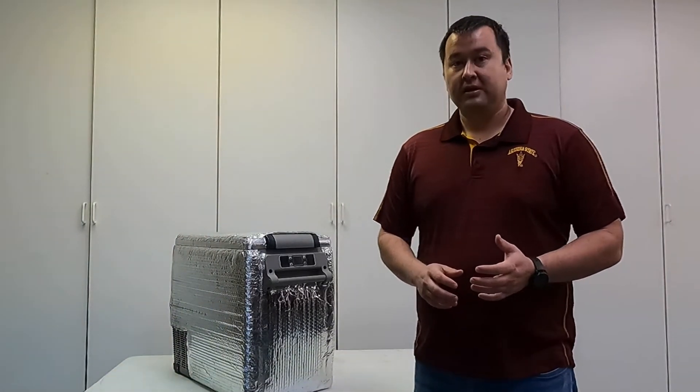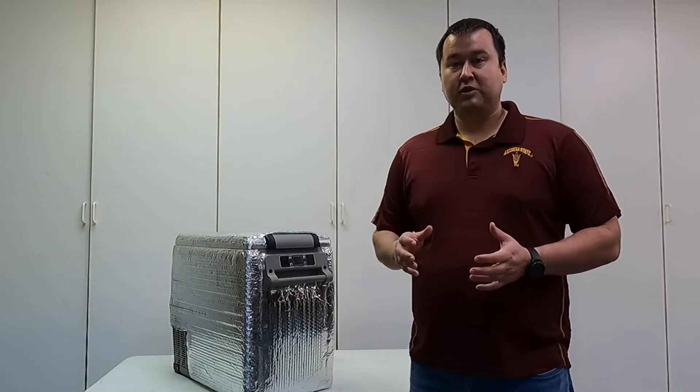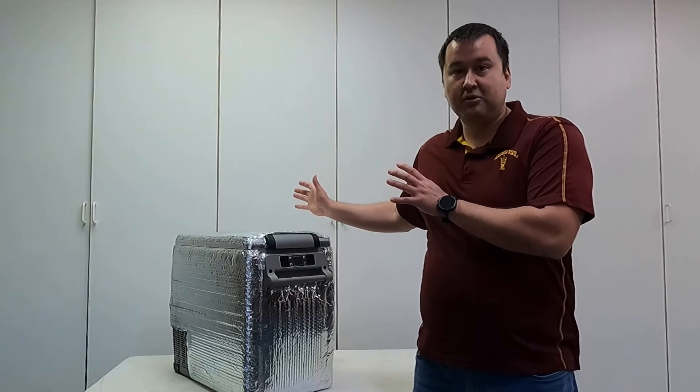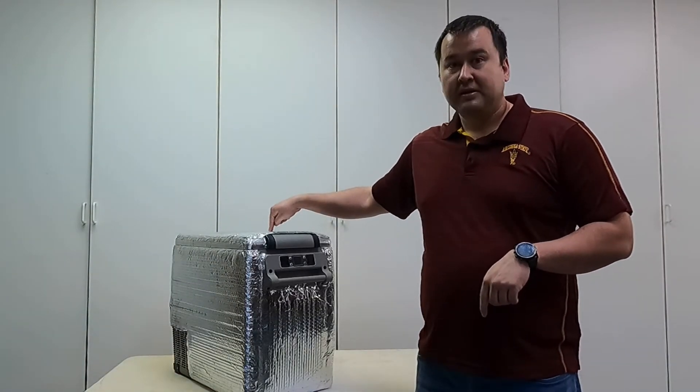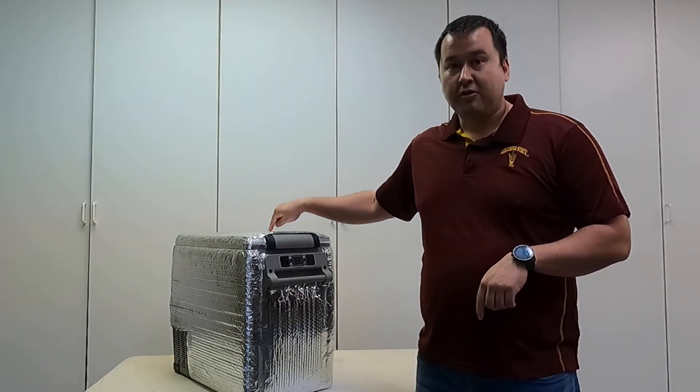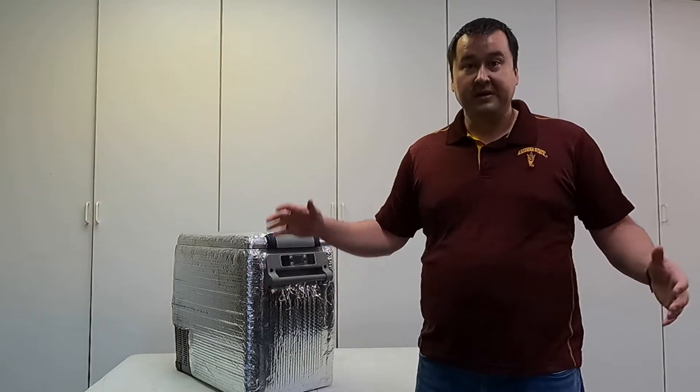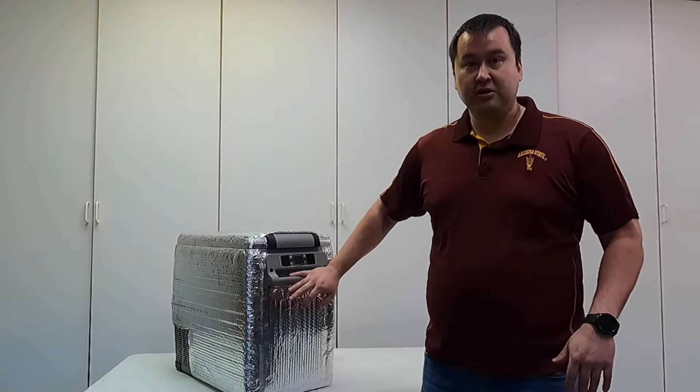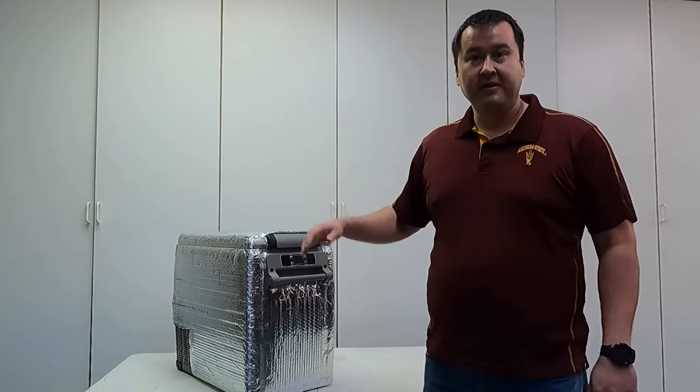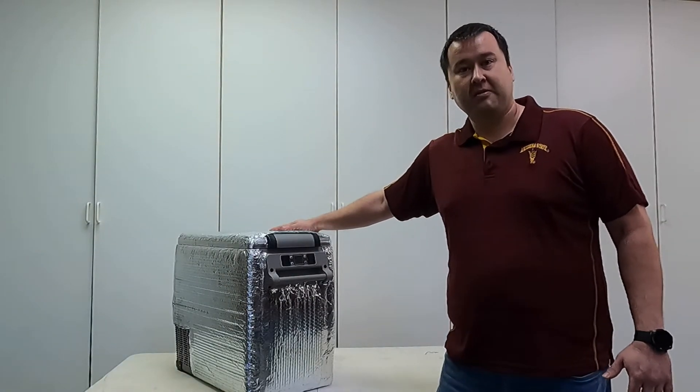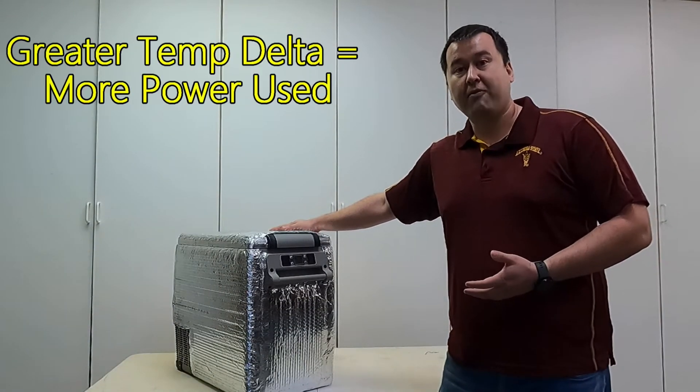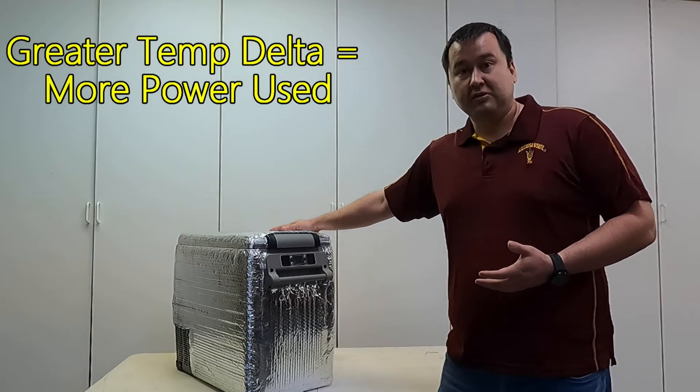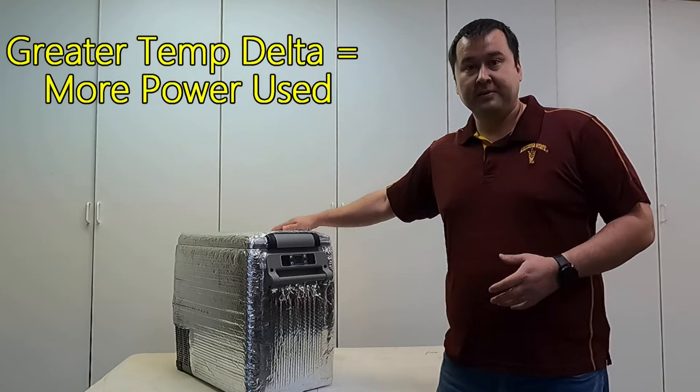The duty cycle is also a function of the difference between the outside ambient temperature and the inside temperature. So the greater the difference between the outside and inside temperature, the more power this is going to use. If I use this in a hot desert climate, it's going to use a lot more power than if I used it in a cooler mountain climate.